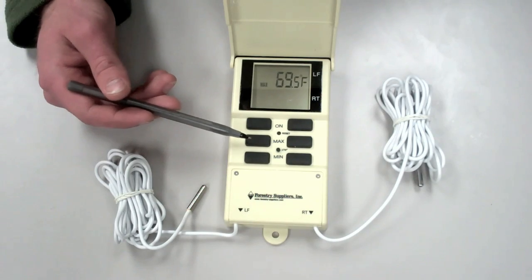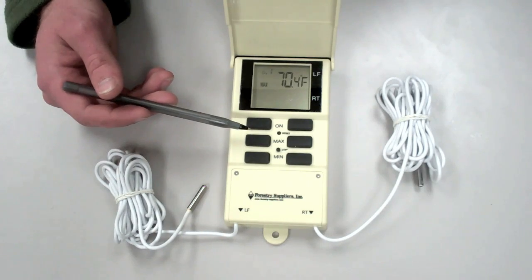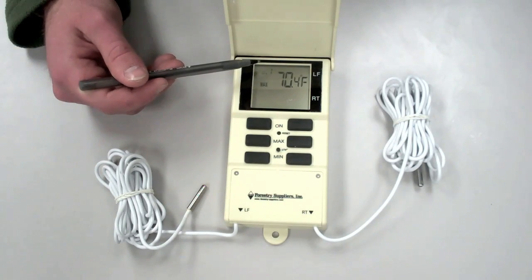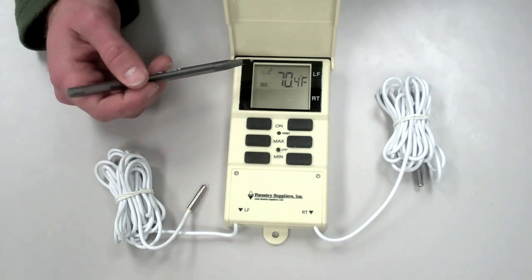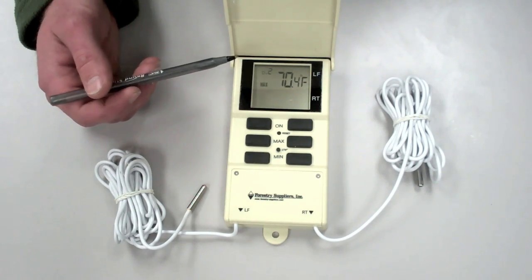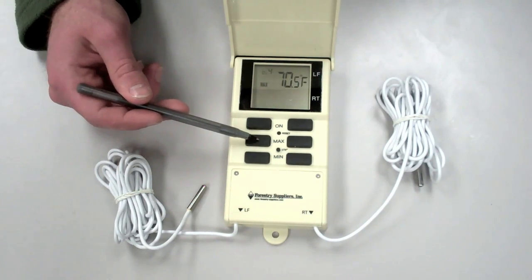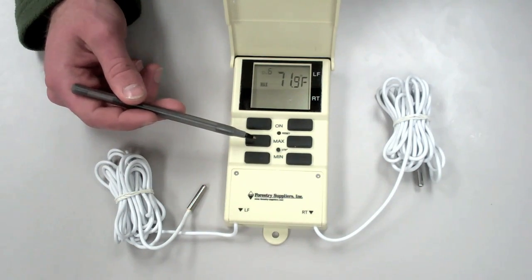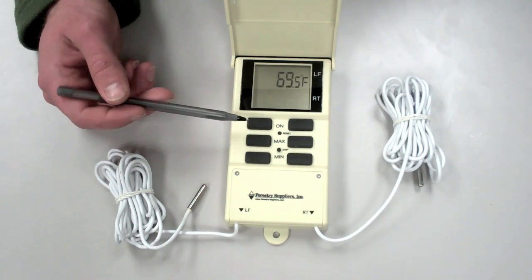Back to max. If we push the maximum button twice, we find the maximum temperature of the 24 hours directly previous to the current time — that is, day one, the first day's maximum temperature. By pushing the button again, we get day two's maximum temperature, the 24-hour period previous to the first day. By pushing this sequentially, we can go back in time and find the maximum temperature of each day as recorded back to six days ago. Pushing the button a final time gives us the current temperature again.